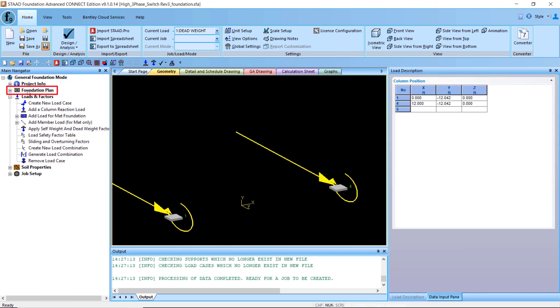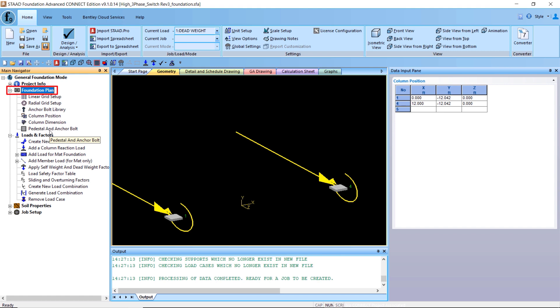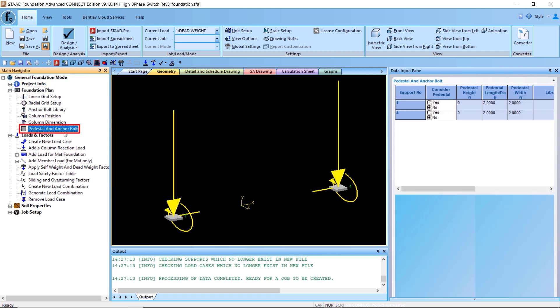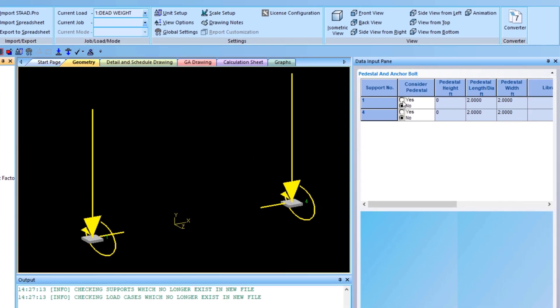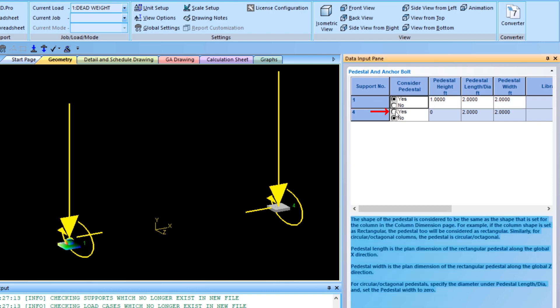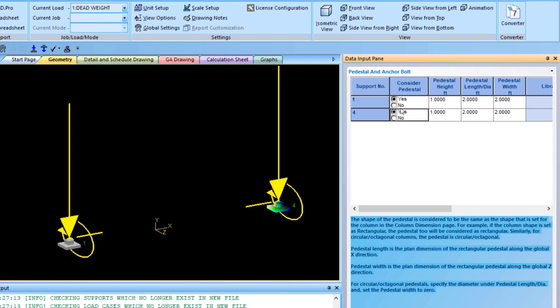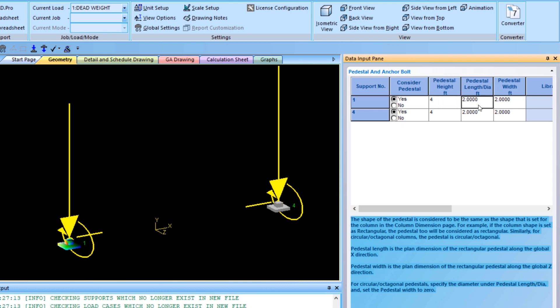Now let's go to our foundation plan and add in our pedestal dimensions. First we need to say that we would like to consider a pedestal for our foundation design, so we include the pedestal from this menu. Then we put in the dimensions of our foundation pedestal, which will be a four-foot height, and two feet by two feet wide — a square pedestal.